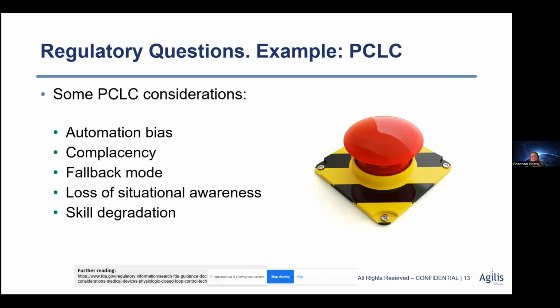Fallback mode. This is an interesting one. Fallback mode is the mode of operation that the system falls back into when something goes wrong. So it could be a mechanical failure. It could be something where the system is stopped. There's a fault, right? So what mode does it go into at that state? And the example of that we talked about earlier was the infusion pumps, right? So when you turned it off, the fallback mode in the system was to just go into a free flow. You need to be super clear that the user understands what that fallback mode is, right? Because that misunderstanding led to a considerable misalignment in the way the system was performing versus what the user thought was happening.